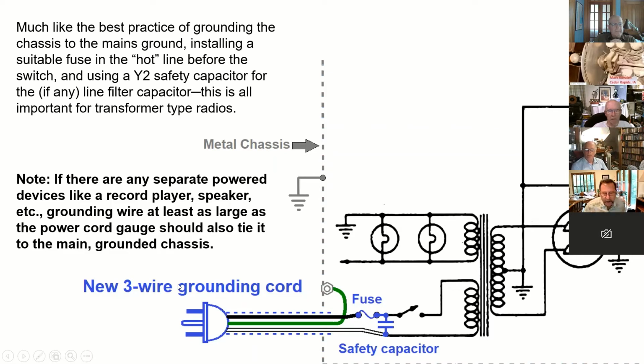If there's anything, we can use Y2s for everything then, right? In my opinion, yes. Okay. Because the Y2 is designed to fail open. So if there's a lightning strike on the line or nearby and you get a spike, this thing will pop open, may or may not blow the fuse. Worst case scenario, you lose some line filtering and start picking up noise on your radio. Okay.